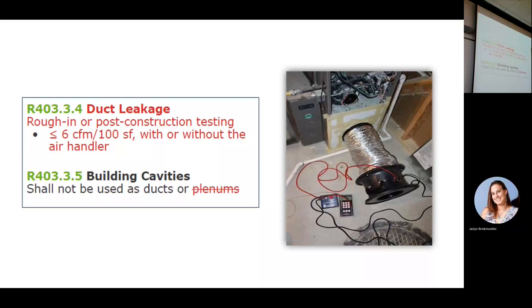So duct leakage, this is the one that we needed to make sure we talked about. Very similar to blower door testing the house, but duct blaster testing is another way we refer to it, our duct system to ensure that it doesn't leak too much. What does the red text mean? That means our legislature allows double the leakage that the code does. But it is what it is.